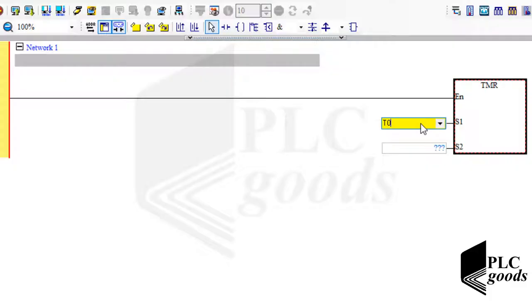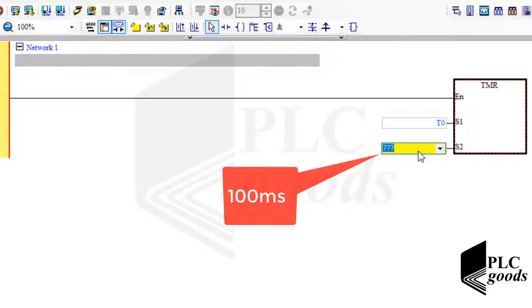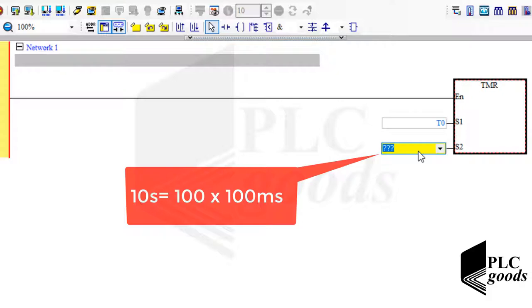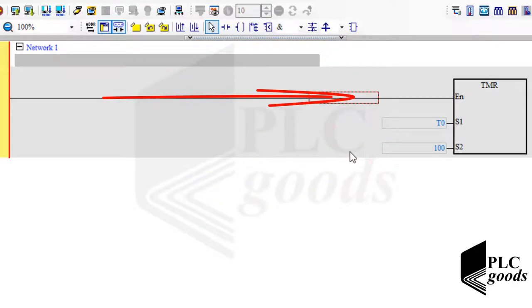The timer's name starts with the letter T and a number starting from 0. The second input determines the desired time. For the first timer T0, we enter the desired time in units of 100 milliseconds. For example, 10 seconds equals 100 × 100 milliseconds, so I have to write the number 100 if I want 10 seconds.